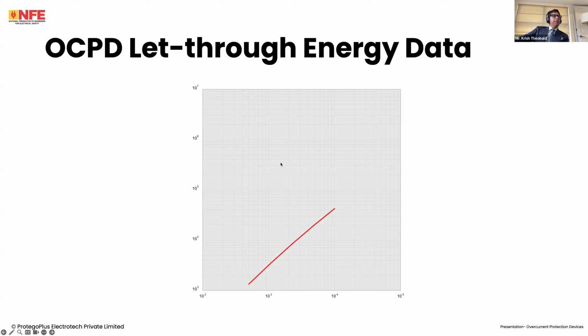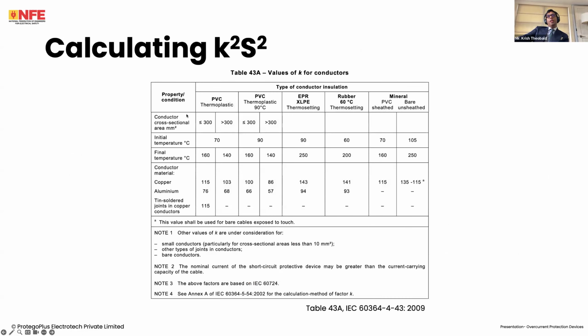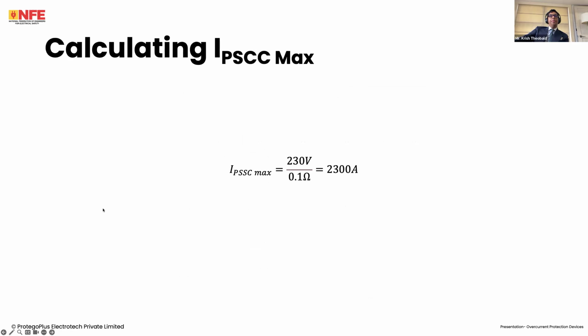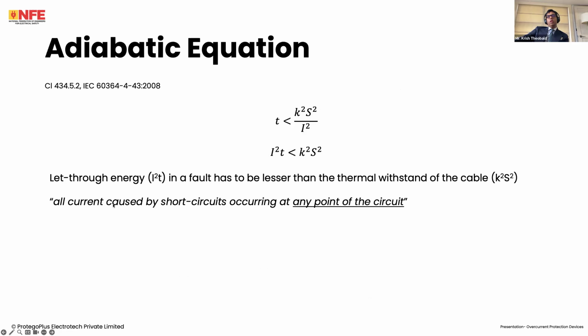I should have the coefficient. Why do I not have the coefficient? It's here. These are given. So for a PVC cable up to 300 square mm, we consider 115 for copper, 76 for aluminium. For an XLPE cable, we consider 143 for copper, 94 for aluminium, and so on and so forth. That is your K.